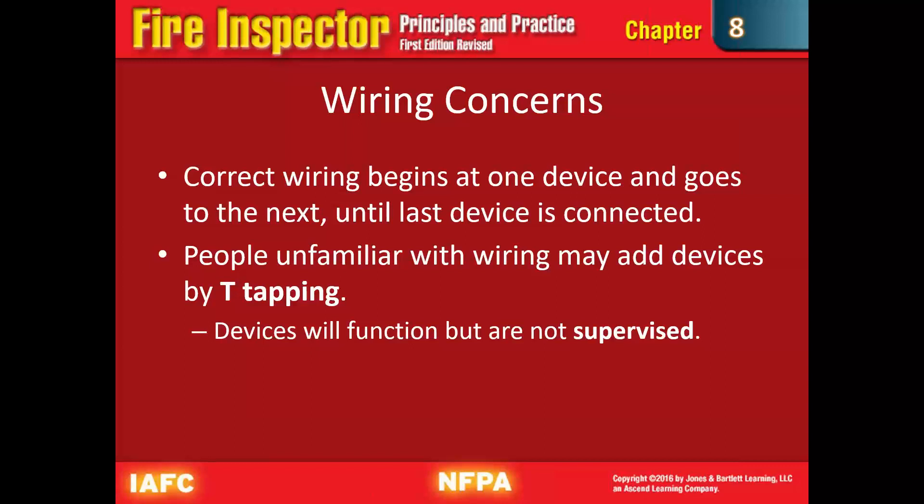Because fire alarm systems are electrical devices, wiring is a concern. Correct wiring begins at one device and goes to the next until the last device is connected — they're all chained together. People unfamiliar with wiring may add devices by T-tapping, which will function on site but won't be supervise-able. During an inspection, check the wiring to make sure they're using the proper gauge wire according to manufacturer specs and NFPA 72 — you can look and find examples of improperly installed wiring.